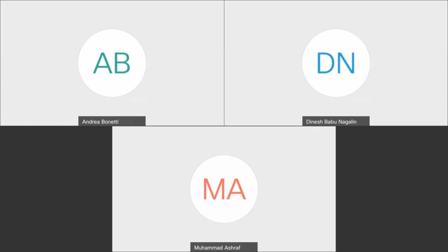It does only standardize that the trip from zone 1 has this norm, that zone 1 is called PDIS. The trip is called PTRC.op or something like this, I don't remember. Start is called ST, for example. You can raise it up and down, and when you raise it up, you simulate the relay tripping. But you don't simulate it because voltages and currents are generated and the relay is measuring them, calculating the impedance, comparing with the settings, and deciding to trip after the timer. You are just raising the signal, which is okay because that signal will send the GOOSE message, and that is what you want to test. You want to test the GOOSE message.